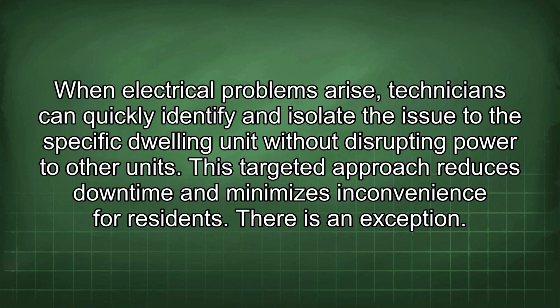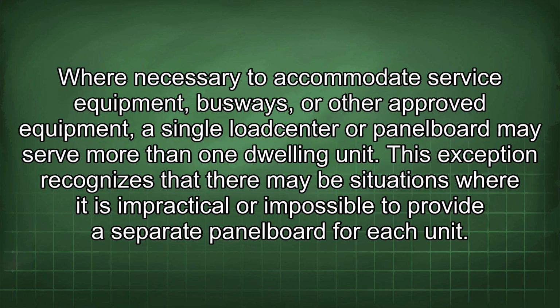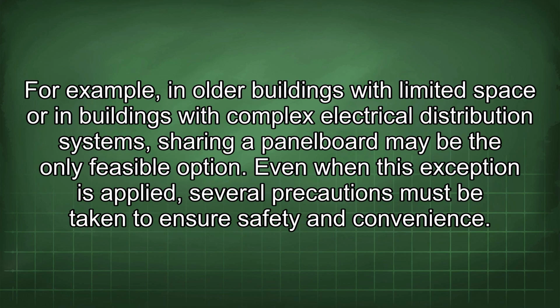There is an exception. Where necessary to accommodate service equipment, busways, or other approved equipment, a single load center or panel board may serve more than one dwelling unit. This exception recognizes that there may be situations where it is impractical or impossible to provide a separate panel board for each unit. For example, in older buildings with limited space or in buildings with complex electrical distribution systems, sharing a panel board may be the only feasible option.